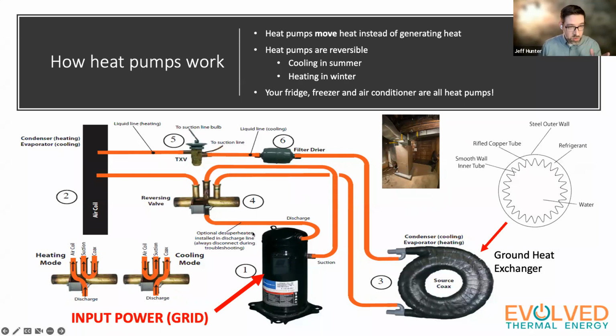A desuperheater sits right here, looks kind of like this coil, same kind of profile, just a little smaller, and it ties in right here, where there's really hot gas coming off of the compressor. The desuperheater looks at this hot gas line and says, when it's really hot, there's extra heat there—I'm going to turn on my little pump and take some of that heat and dump it into my hot water tank.